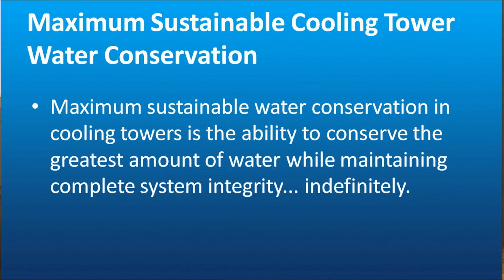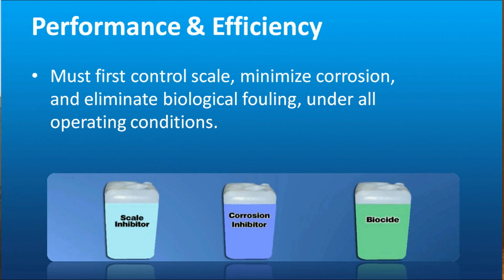So what is maximum sustainable cooling tower water conservation? In cooling towers, it's the ability to conserve the greatest amount of water while maintaining complete system integrity indefinitely. But first, you must control scale, minimize corrosion, and eliminate biological fouling under all operating conditions. That's generally done with a scale inhibitor, a corrosion inhibitor, and a biocide.